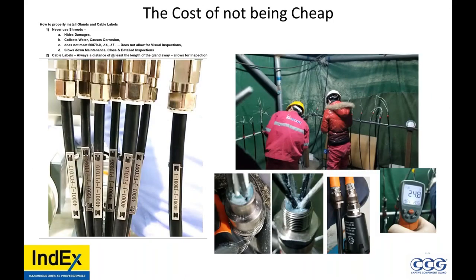Now, what's the best way to do things? Well, use nickel-plated brass with no shroud, so a high quality gland, or even a decent gland, and put the cable tags further back so you can actually inspect the glands. You can back them off. Give it 120 mil. So without a shroud, you're not hiding the damage. You're not collecting water or causing corrosion. You're meeting the requirements of 60079-14 17. You're not slowing down maintenance, and you're not stopping inspections. This is good for the end user. The more they see problems happen, the more they can plan to repair things. But if they can't see it, out of sight, out of mind. Cable labels, always keep a distance of the length of the gland away from the gland.